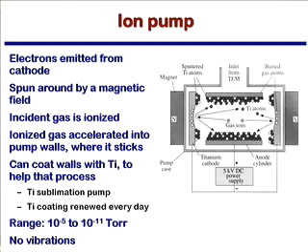But again, you have to first use a roughing pump and then a turbo pump to get down into the 10 to the minus 5 sort of regime. Usually in the modern TEM, you'll be using ion pumps up in the gun all the time. You'll use ion pumps local to the sample after you've introduced the sample and used the combination of the roughing pump and the turbo to back everything out. And again, these things have no vibrations, so they don't interfere with your work in terms of moving the column around and shaking the atoms that you're trying to take a picture of, okay?